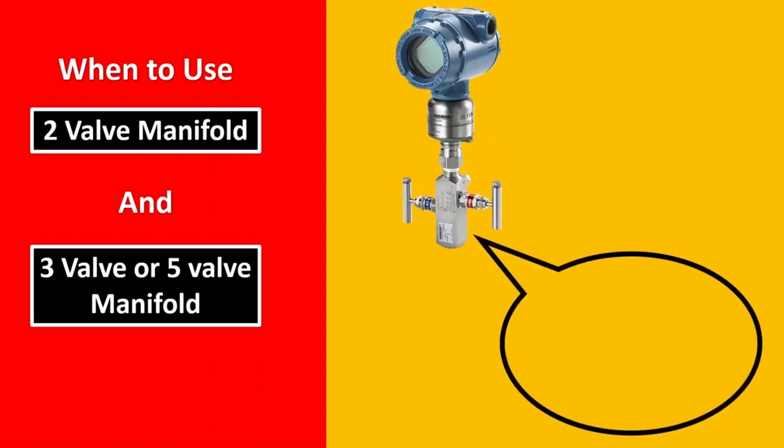Remember that for a transmitter, 2 valve manifold is very simple. You have 2 valves to it, one is going to be your isolation valve, the other is going to be your vent and drain valve. This is how it looks in the real world and this is the diagrammatic representation that you can draw.